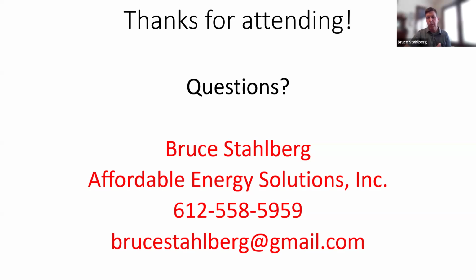When you talk about static pressures, most of the contractors are totally aware of it, although I have had some technicians say they went through school and didn't really get much information about static pressures, which is kind of crazy. But contractors are aware of it, they're just not testing it. So when I go out to a system, I don't see the test ports. Our agency now is doing it with frequency. We're trying to get our auditors to do it on the front end of it.